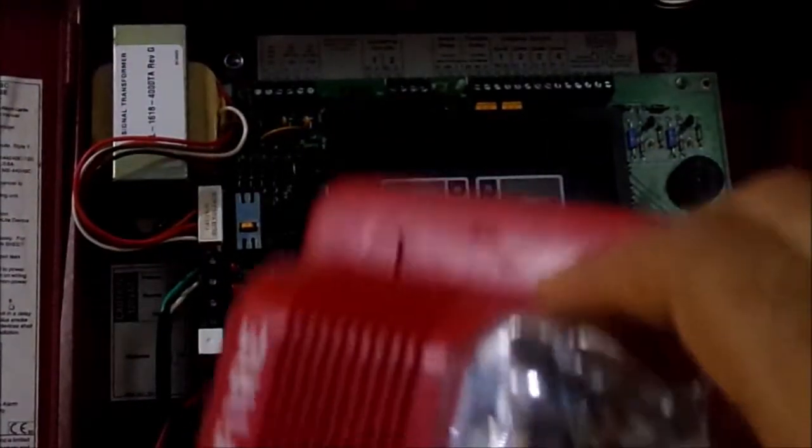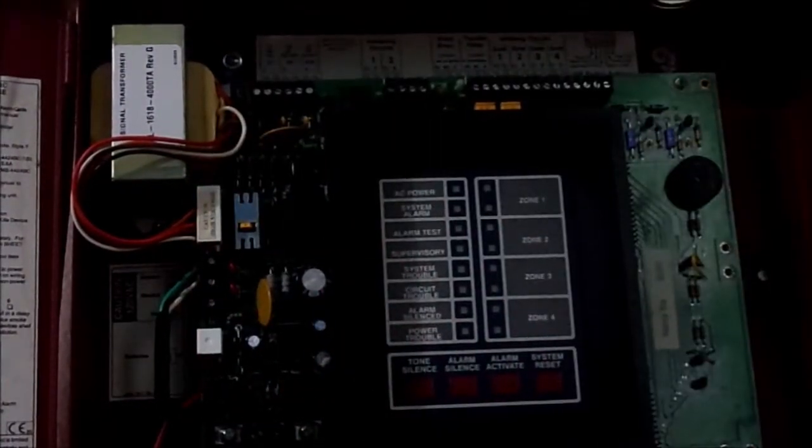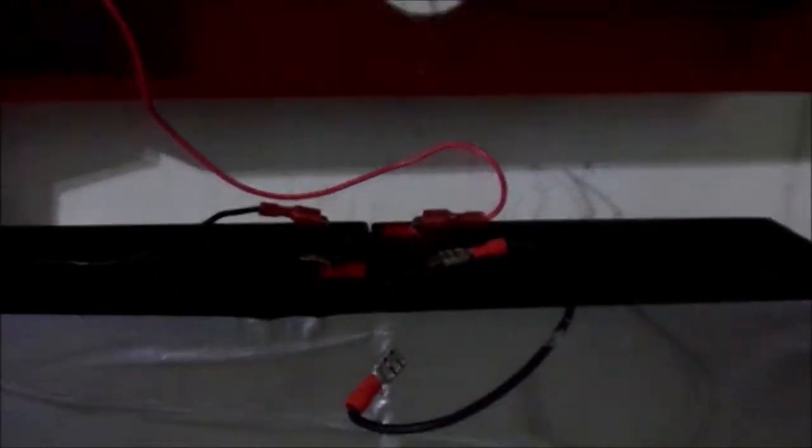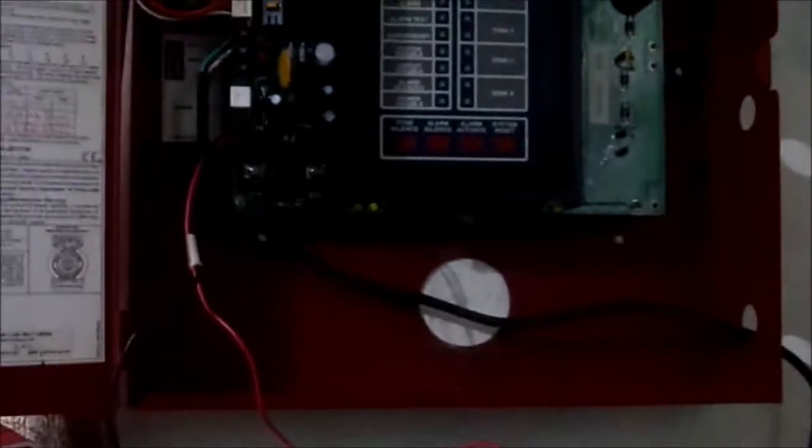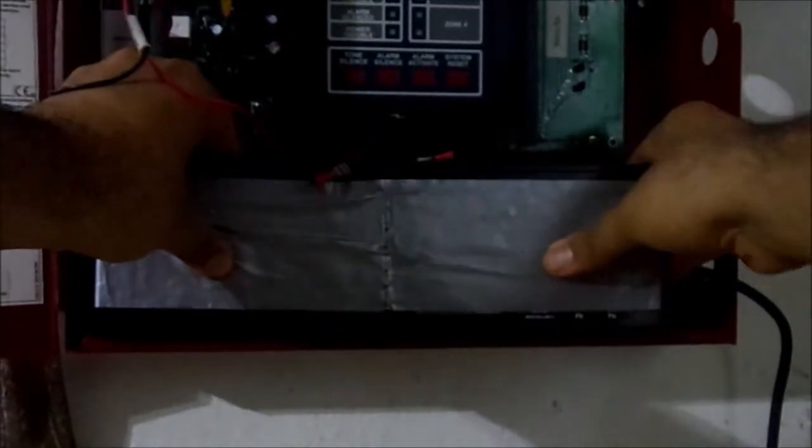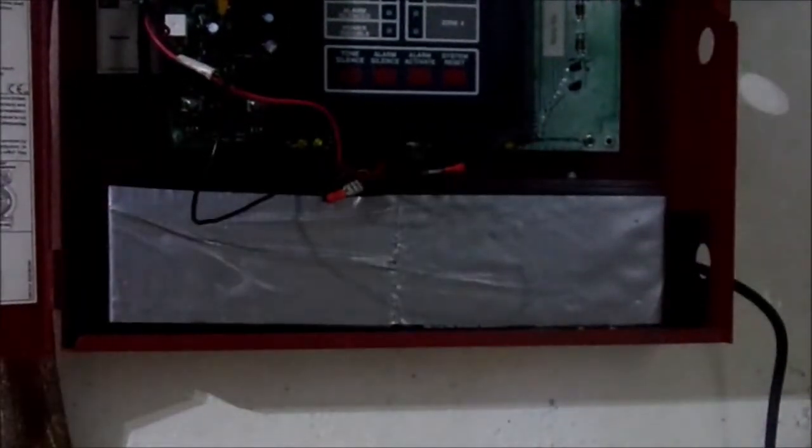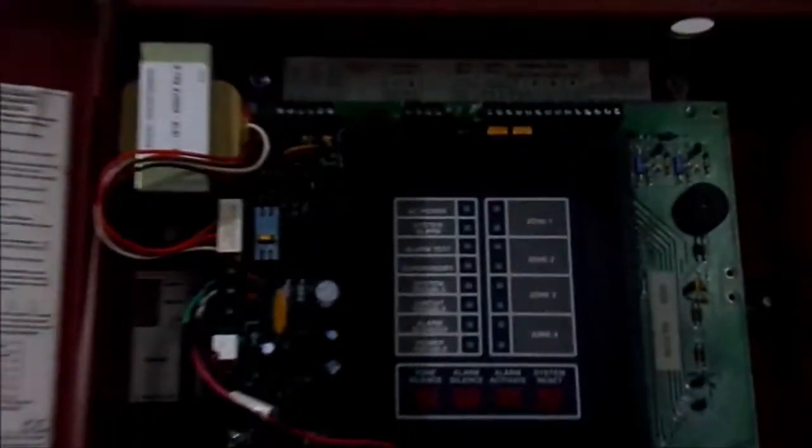Same thing over here, but for these, which you saw earlier. This part of the side is for initiating devices such as pull station here. And once again, the first over here in the middle is for these. Now you know how this works. For the rest, that's the piezo right there where it makes all the beeping noise. And this is the battery. This is important because you will need the battery. Otherwise, your panel will be staying in trouble and be making annoying noises. To wire the battery, you want to make sure you put the positive and negative over here. And then make sure you have a loop so that when you plug it in, you see a spark and you see a little beep, the panel will turn on. That's why you need the battery. So, I'm going to put the battery up here. And I'm going to get into how to wire the notification points.